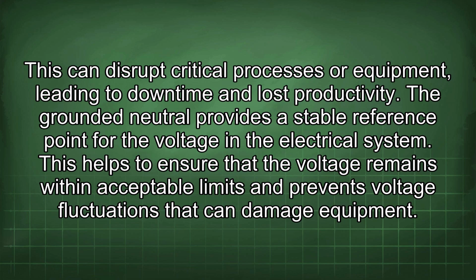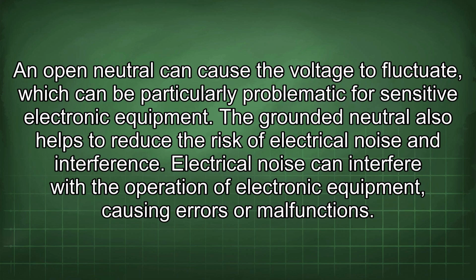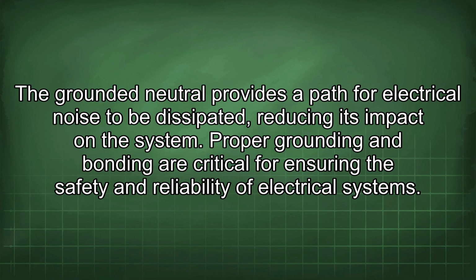The grounded neutral provides a stable reference point for the voltage in the electrical system. This helps to ensure that the voltage remains within acceptable limits and prevents voltage fluctuations that can damage equipment. An open neutral can cause the voltage to fluctuate, which can be particularly problematic for sensitive electronic equipment. The grounded neutral also helps to reduce the risk of electrical noise and interference. Electrical noise can interfere with the operation of electronic equipment, causing errors or malfunctions. The grounded neutral provides a path for electrical noise to be dissipated, reducing its impact on the system.